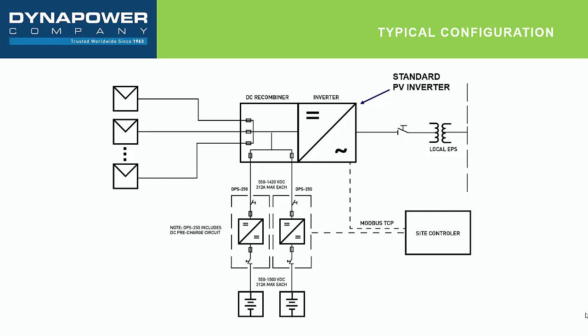And also shown here, you'll see that these DC-DC converters can be operated in parallel, getting back to the concept previously noted about design flexibility. So you can run many of these in parallel, as many as you need, in essence, to get the right ratio of storage to your PV array size or your PV inverter size.